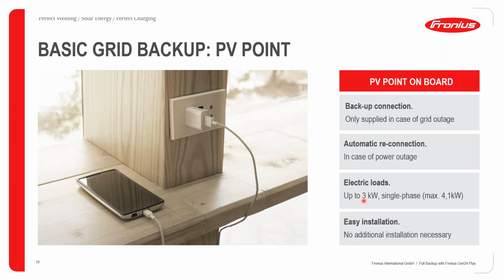So with the PV Point, as I said earlier on, it provides an inexpensive ability to achieve basic backup power. Okay, and it's only activated when the grid goes down. It doesn't matter which Fronius Gen24 Plus inverter you purchase, each one will give you a single phase output of 3 kilowatts max. However, you can get a maximum of 4.1 kilowatts for a very short duration of time, between 4 to 5 seconds. And that's very handy for starting any device that has a high startup current, such as a fridge, for example.